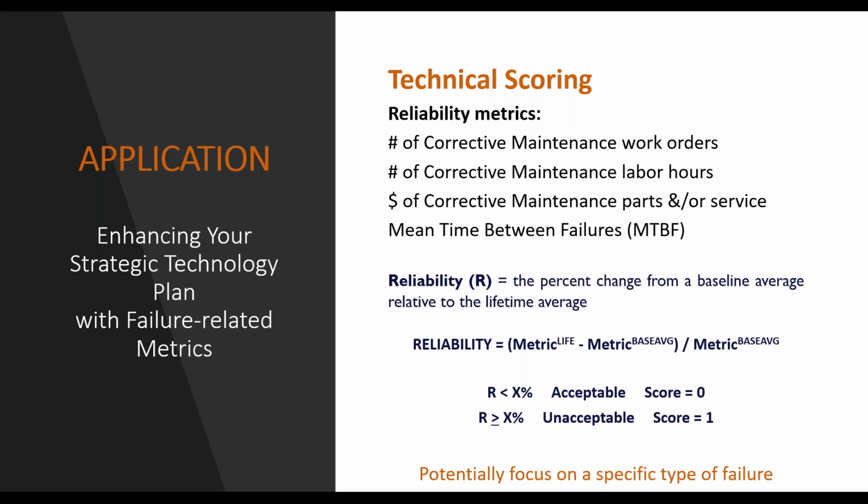You may say, in my radiology world, this metric is most important: the number of labor hours, because they're reflective of uptime and downtime, like a surrogate. And that's a revenue generating department, so maybe I want to focus on that. Maybe for my general fleet items, defibs, pumps, whatnot, I want to use a more general mean time between failure or the dollar spent or the count. Maybe it's more general for that. Some devices may need their own.